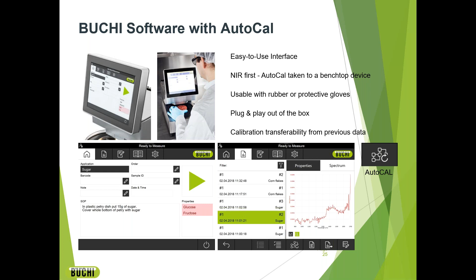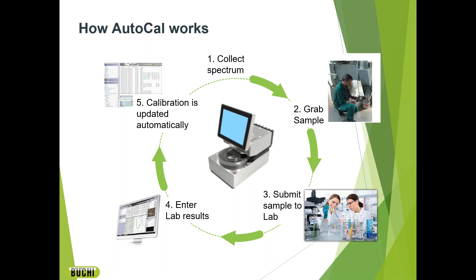One, a sample spectrum is collected. In the NIR online setting, a grab sample is obtained via a sample loop or a sample thief. The sample is then sent off to a lab for primary analysis. The results are entered into the system. Calibrations are created or updated using the AutoCal function, which is activated by pressing one button.